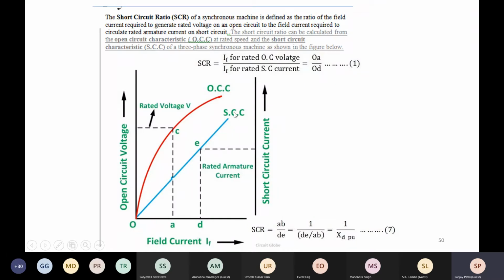Then when you put a short circuit on the generator, to drive the rated current in the short circuit, what is the excitation required? That becomes another parameter. So the short circuit ratio is basically the field current required for generating rated open circuit voltage. Below, the denominator is the field current required for circulating the rated short circuit current. This becomes the short circuit ratio, and if we go by the mathematical equation, this actually becomes the inverse of your direct axis reactance or synchronous reactance. So short circuit ratio, as a thumb rule, is the inverse of reactance. What it means is, the higher the reactance, the lower the short circuit ratio.